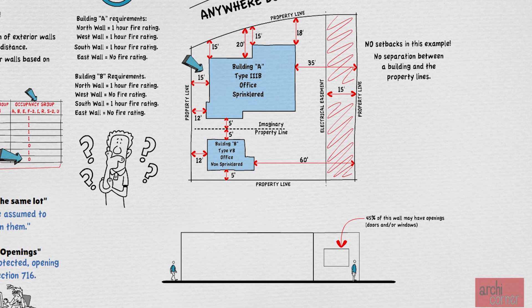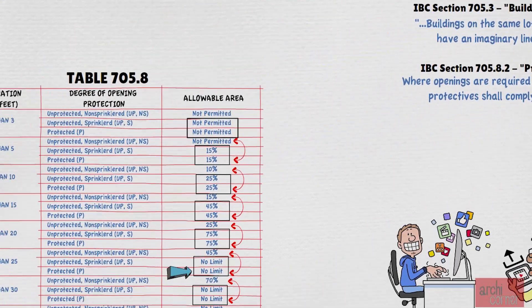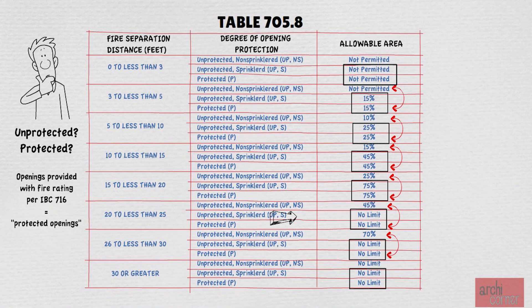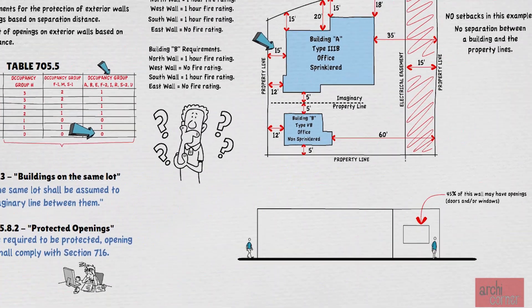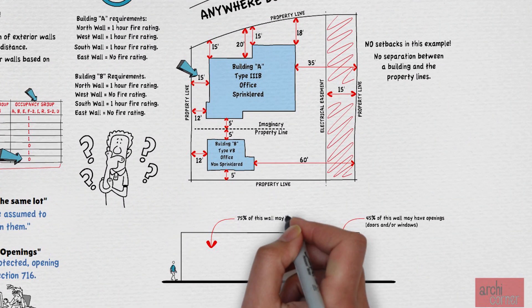Now that you know this, the next wall is much faster. Going back to the next wall, this wall is 15 feet away from the property line. Per the table, if the wall is between 15 feet to less than 20 feet away and has unprotected openings — or in other words, non-fire-rated openings — since this building is sprinklered, we are allowed up to 75% of openings in the wall.